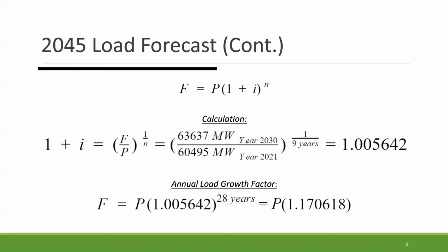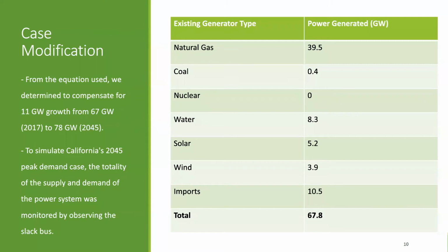You can see in our calculation process that we took values from the previous slide, from the years 2021 to 2030, and then used the 28-year gap to account for the given case from 2017 to 2045. The final annual load growth factor, as seen at the bottom, was 1.17, and this multiplier would be used to multiply the load annually.